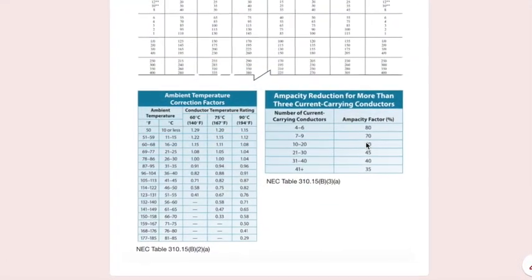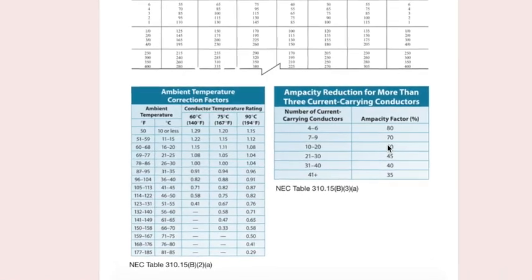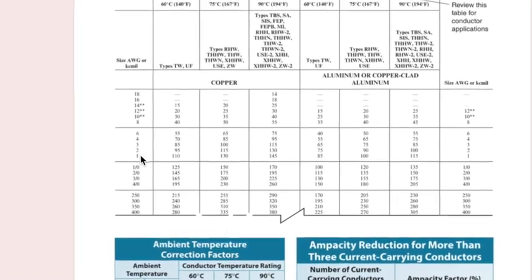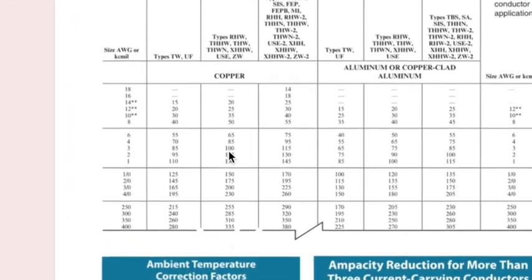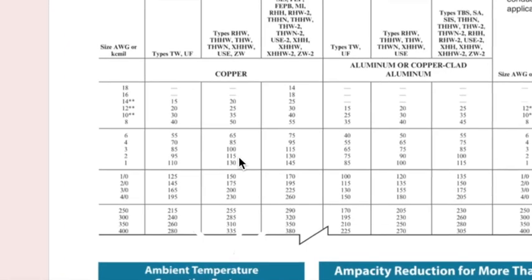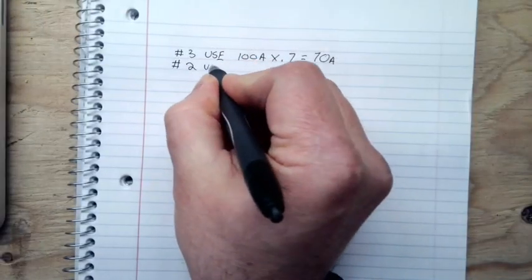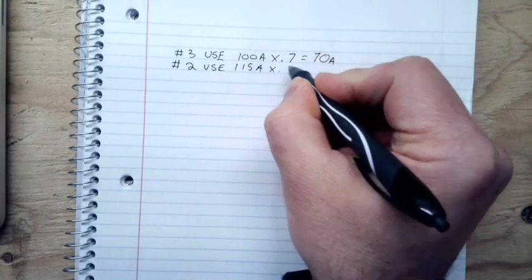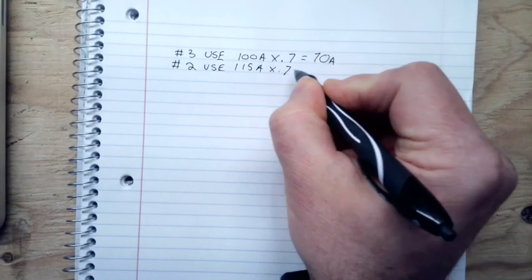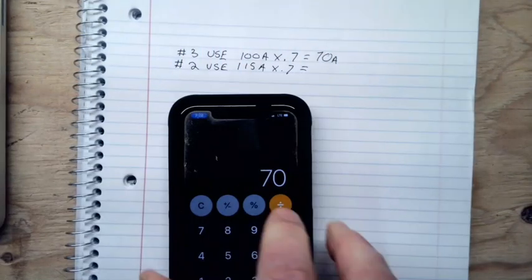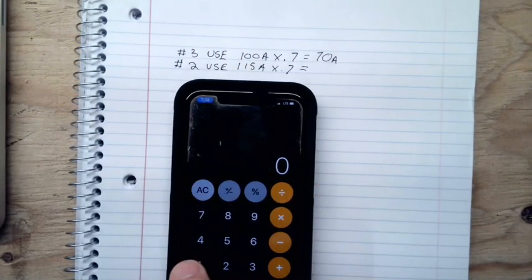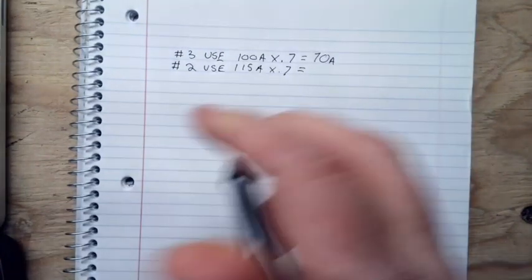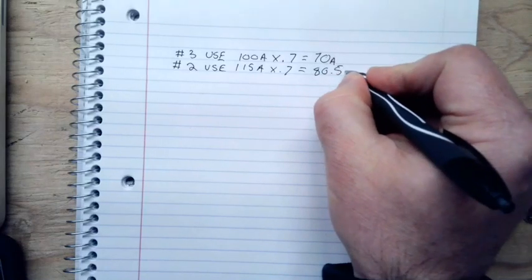So now we just got to keep working what we did before. So I just did a number three at 100 amps. So now we're going to jump up to a number two at 115. Number two U.S.E. at 115 amps. Remember, your adjustment factor will not change. So we're going to go with 115 times 0.7 equals 80.5. Still not anywhere near what we need for amperage.